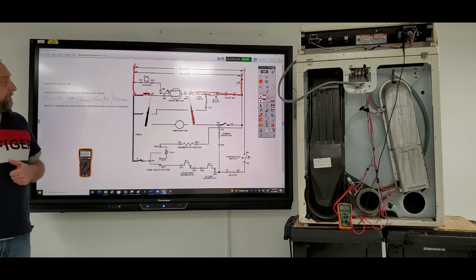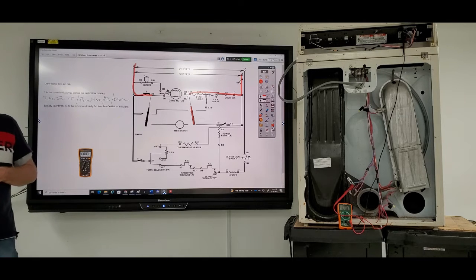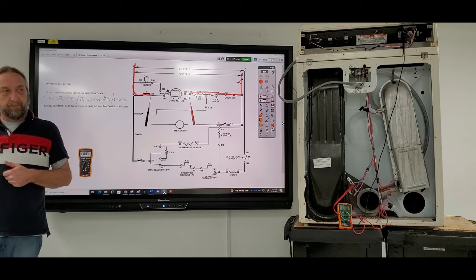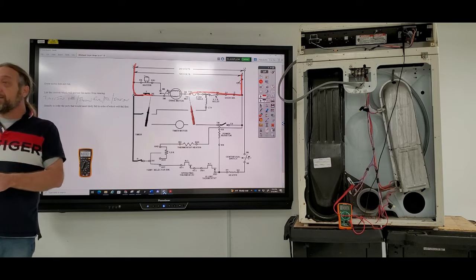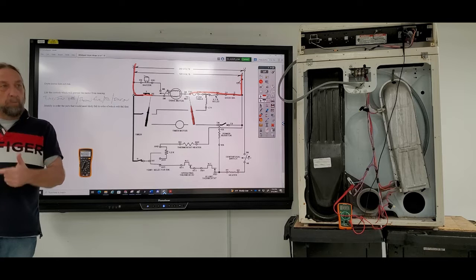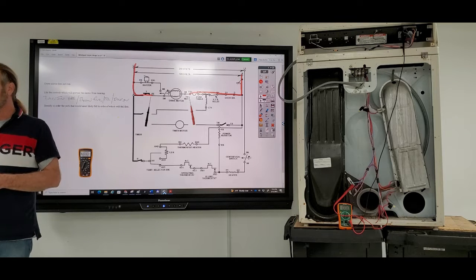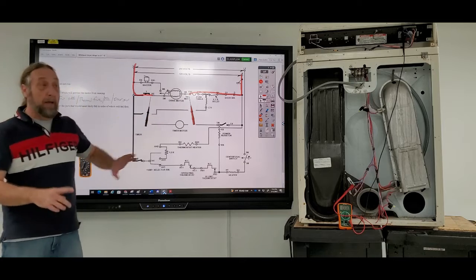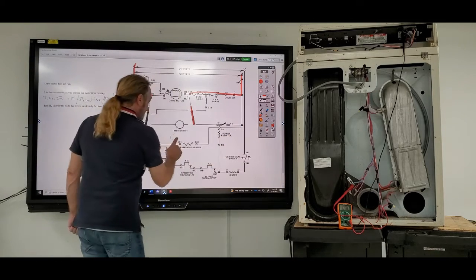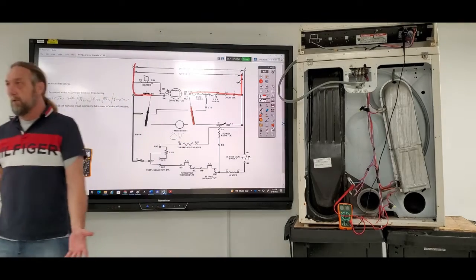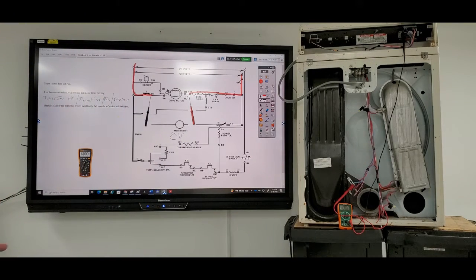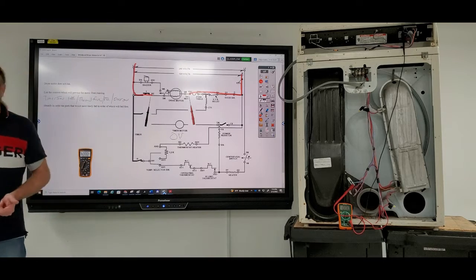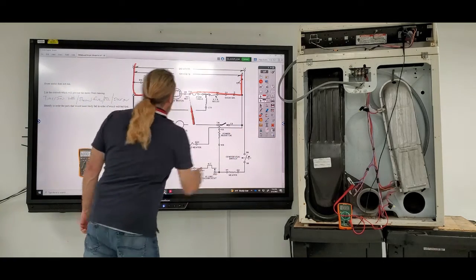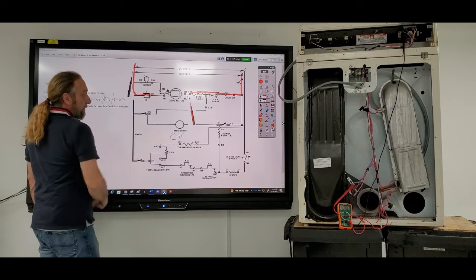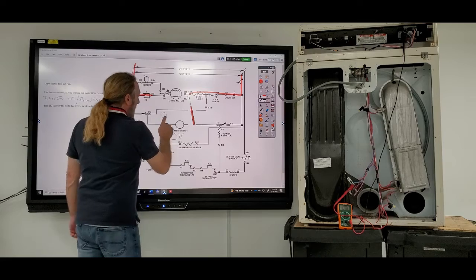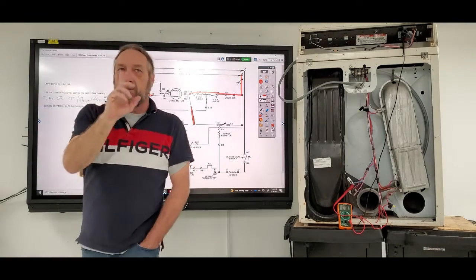And the only reason I do it that way is just in case it's maybe the timer, maybe the fuse, and if not, one gets switched back so you can narrow down who's actually failing. Well, an easy way to narrow down, remember testing circuits, is go back to those 3 screws in the back of the machine. Oh yeah. Because if I'm right here and my meter's telling me 0 volts at this point, okay? I need to know, okay, I don't have voltage there. Where is my voltage? How far did it go inside the machine? If I move one meter lead, this one, to line 1, and all of a sudden now I got 120 volts, then we know on the other side where neutral is the issue.